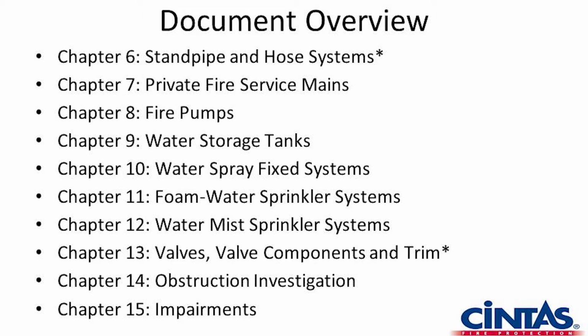Chapters 6, 7, 8, 9, 10, 11, 12, and 13 are covering specific systems. When we talk about NFPA 25, we talk about it being the standard by which we conduct wet sprinkler inspections, whether it's a dry system or pre-action system that doesn't normally have water in it. The end result is we get water from it when we have an activation. Chapters 14 and 15 deal with 13. 13 is applicable to any system because it covers all the valves and components and trims, the corrective action, and the frequencies at which it should be inspected or tested. And then we move into 14, obstruction investigation, and then 15, impairments.